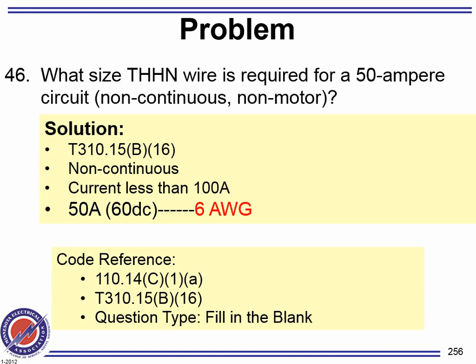Now what if I told you this cable is tied to a piece of equipment that's motor design B, C, or D, or the lugs are rated for 75? What would the answer be? Number 8? Number 8. Does that make sense?